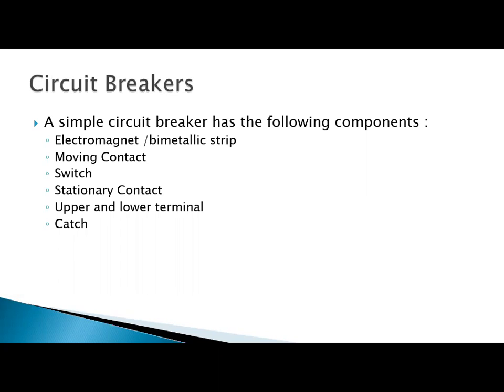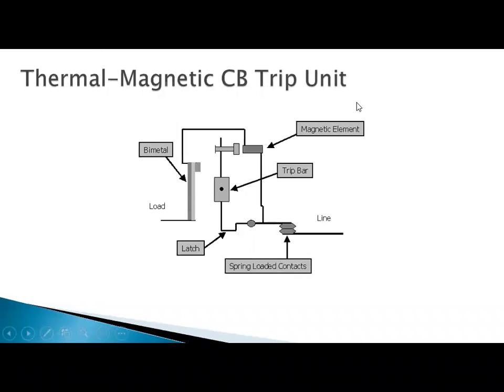It will have a stationary contact. It'll have some terminals that we're going to connect our line side and load side to. And it's got to have a mechanical catch to keep it in place when we have turned that circuit breaker on. So here's a little pictorial of it. These are molded case circuit breakers, and we're going to be looking at different types of circuit breakers today, some that are not molded case. But these are just our regular thermomagnetic circuit breakers that we would go buy right off the shelf, that are probably in our homes or in most of our facilities.